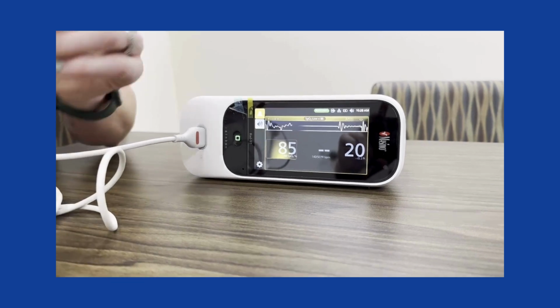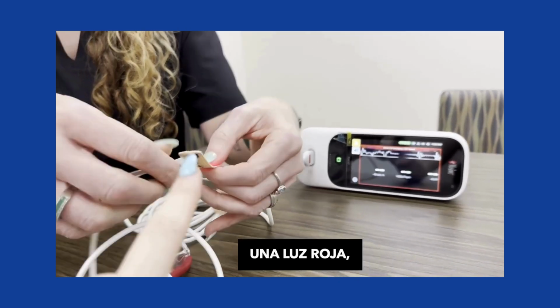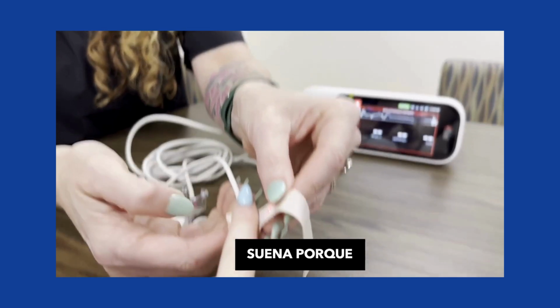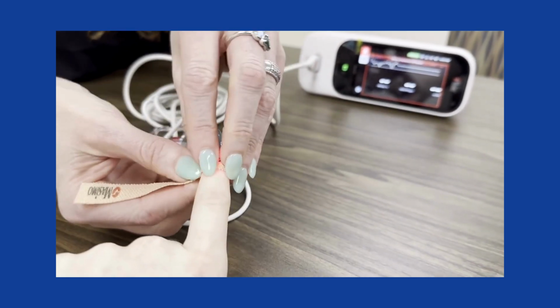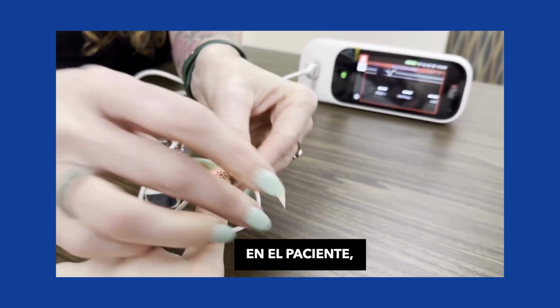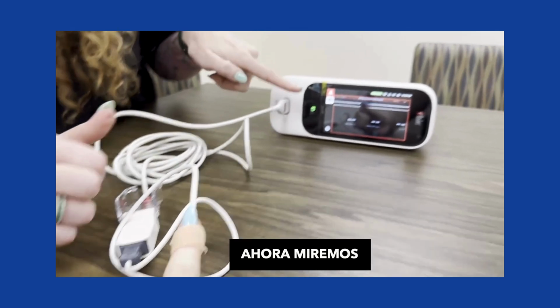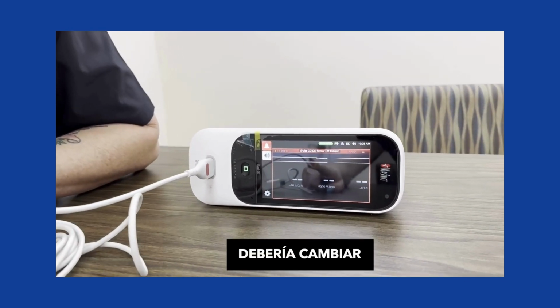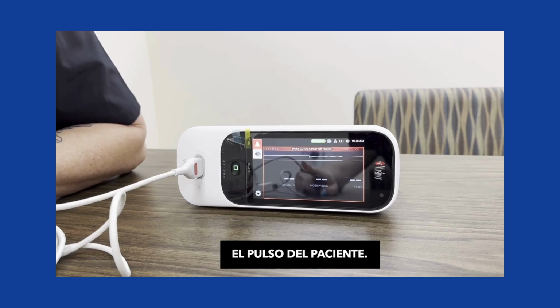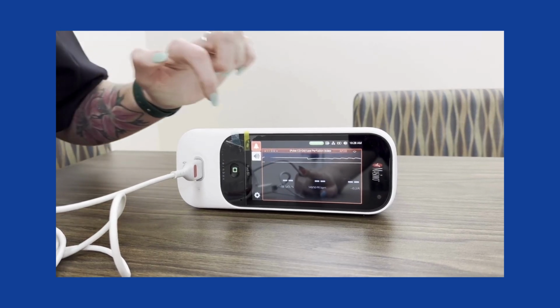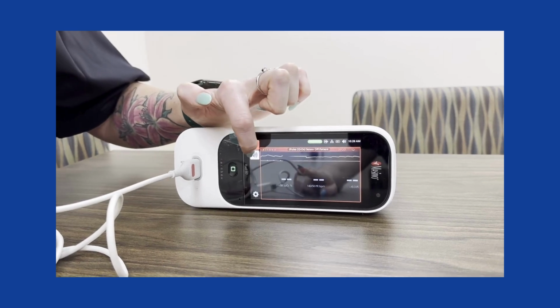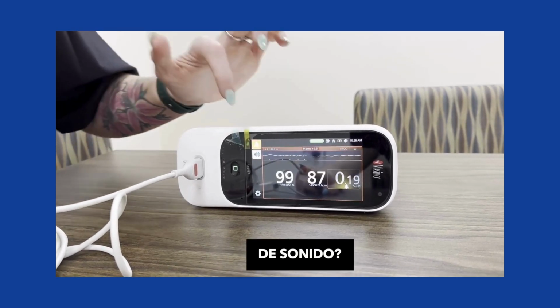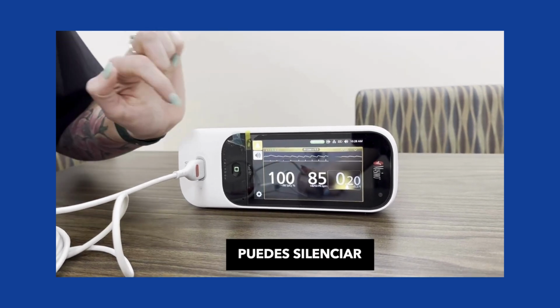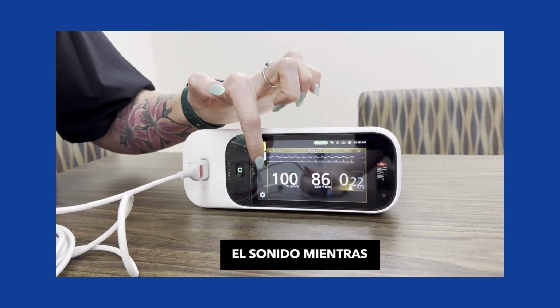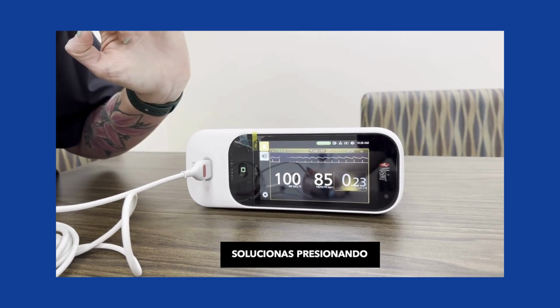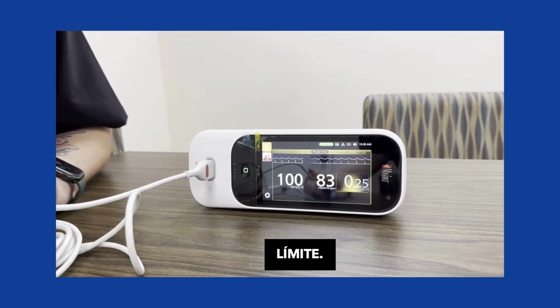All right, so you're going to just put it on the patient. You'll see there's a red light, okay? So it's alarming because it's not detecting anything. So we're going to put it on the patient, okay? And then let's watch the screen. It should change once it picks up the pulse on the patient. While it's alarming, you see this little button here that has a little sound. You can of course mute the sound while you're trying to troubleshoot by pushing that, all right? And it'll give you a time frame.